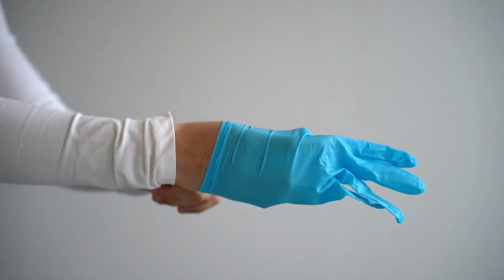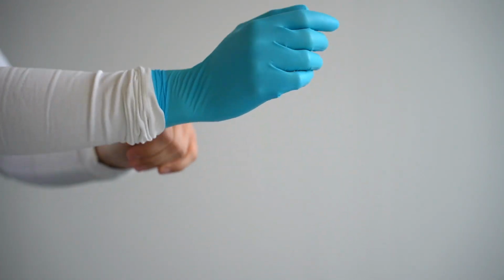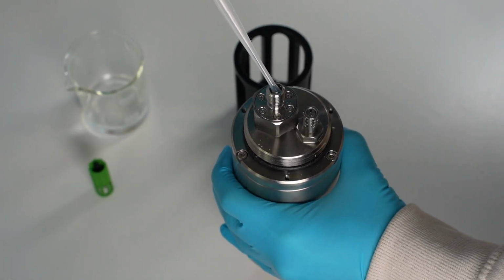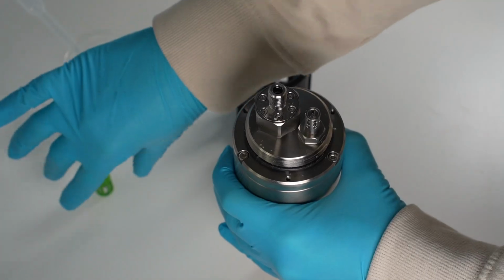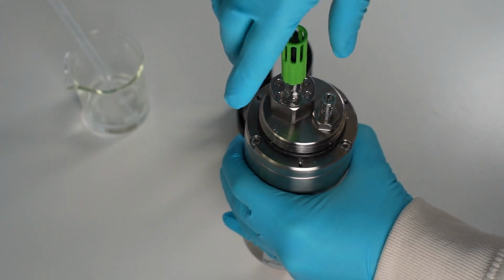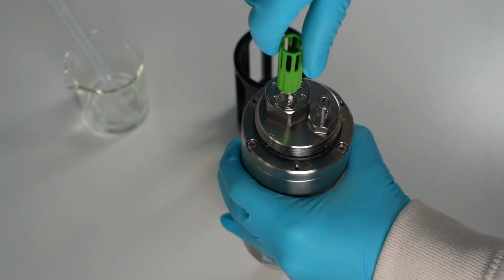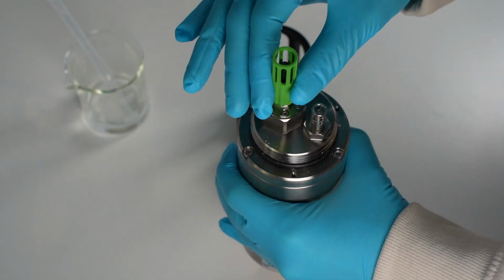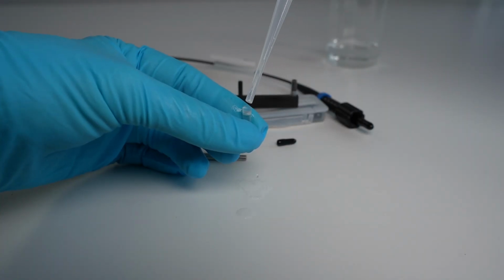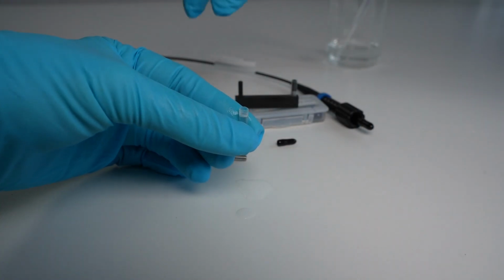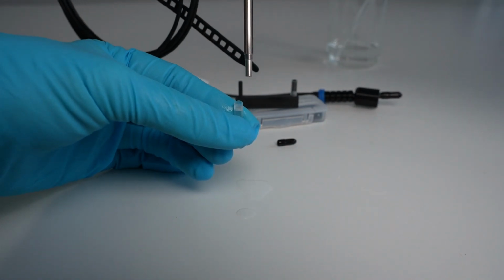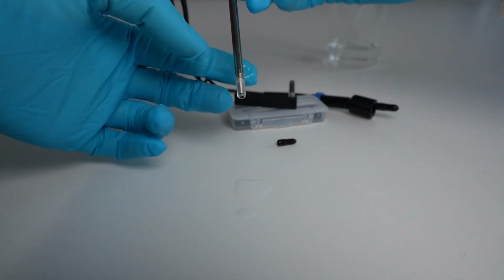It is mandatory to wear gloves to protect the sensor from irreversible damage. Fill the connector completely with deionized water. Ensure that the connector is bubble-free. Insert and secure the sensor with the cap nut. Tightening the nut by hand is sufficient. If you are using underwater fiber-based screw cap probes, ensure that you additionally fill water into the screw cap before connecting them to the sensor tip.